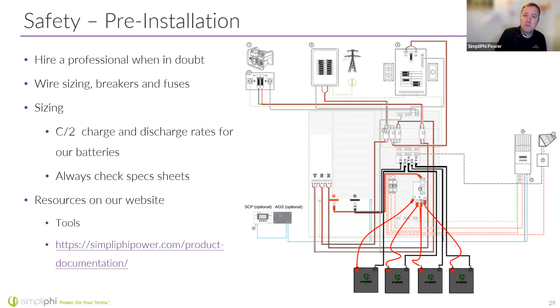We got a lot of information on our documentation page on our website. One thing I'm always really proud of is our integration guides. I talked earlier about how if you have one of our PHI or AmpliPHI batteries, you can put it in with the Schneider, with an Outback, with the Sol-Ark, or with other equipment. We have integration guides that list the order in which those settings need to be changed in the equipment. So if you're going into a Sol-Ark unit, download and print our Sol-Ark integration guide. It'll tell you what screen to program the float, bulk, absorb, and charge/discharge rates. Check out our product documentation tab - we have guides for Victron and a lot of different companies there.